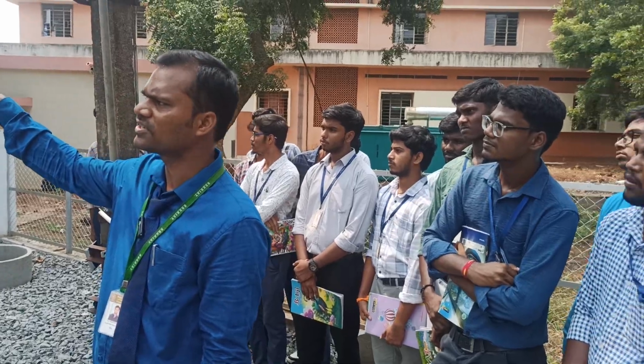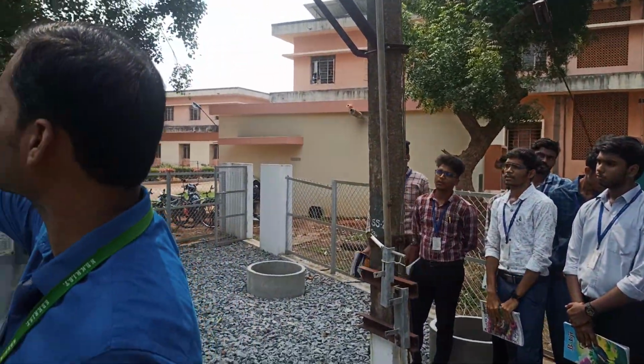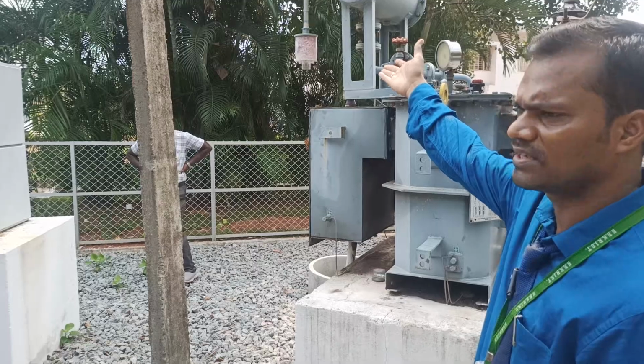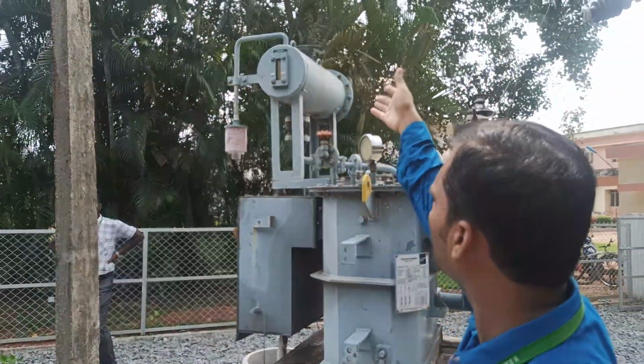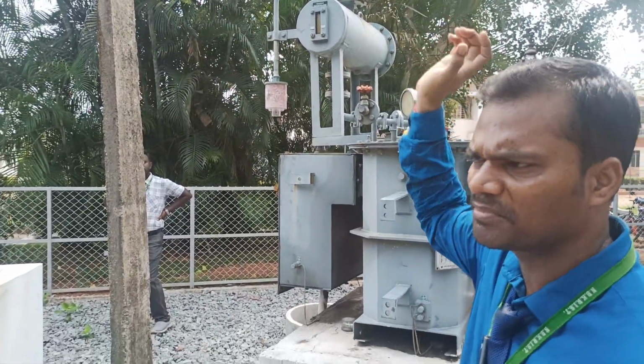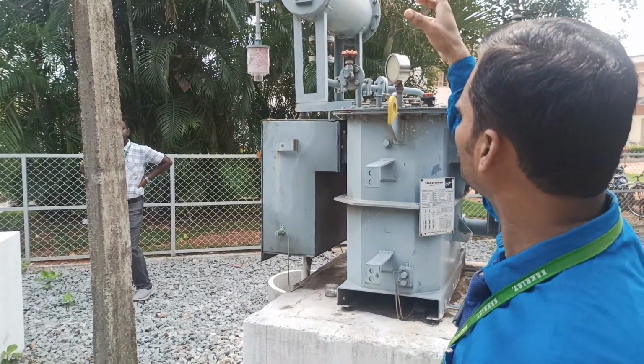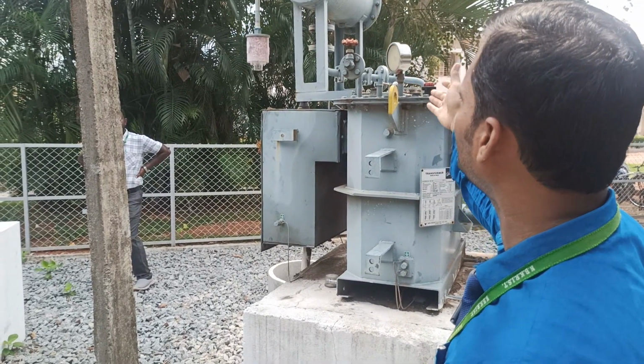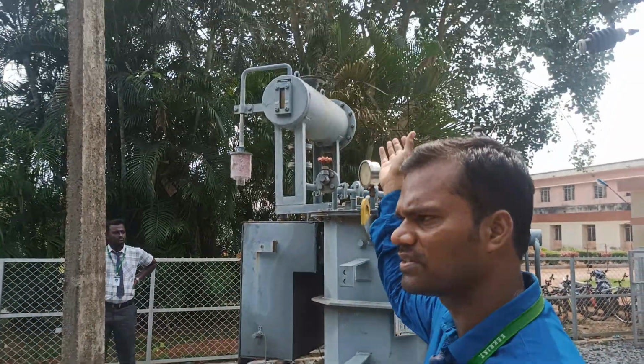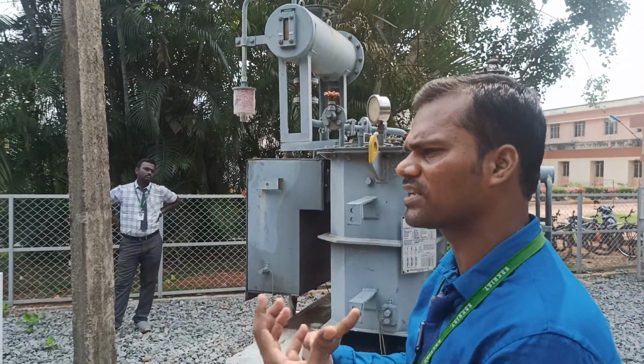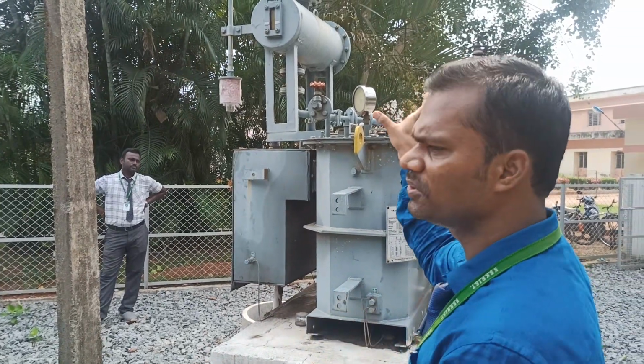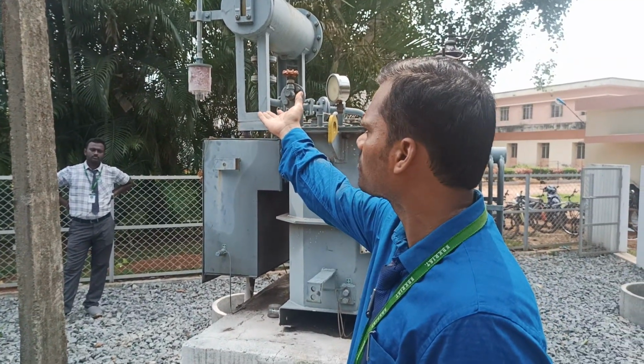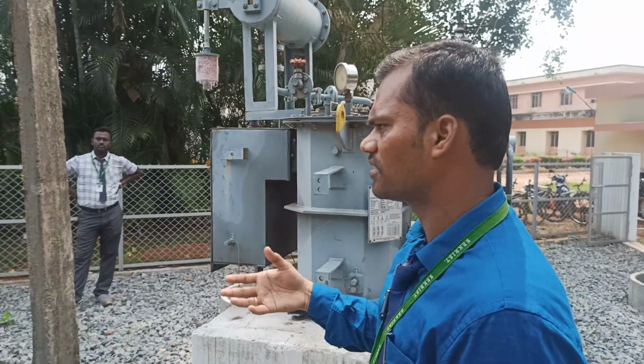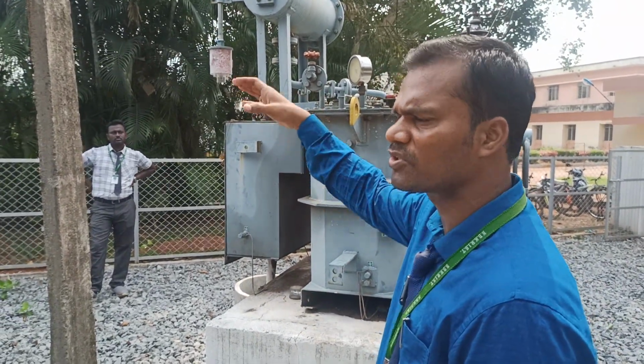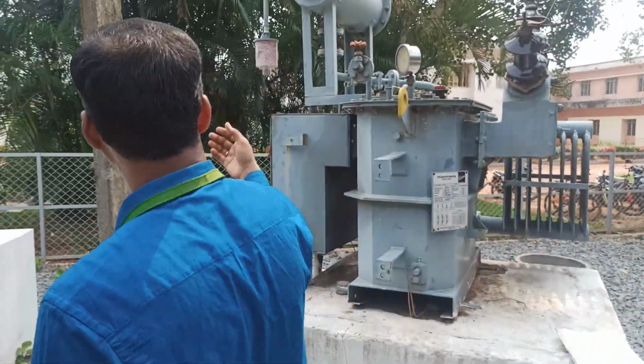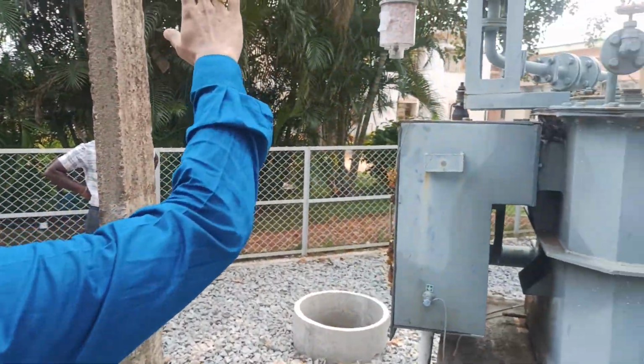So this porcelain will act like an insulator. You must have studied this in the transformer. This is like a breather, where we have silica crystals which absorb the moisture, and at the top what we are going to have is nothing but a conservator tank. Through the conservator tank we have a Buchholz relay. It will try to maintain the required pressure in the tank as well as in the oil. Conservator means balancing. Whatever oil is required, it will try to balance, and it will absorb moisture from the air. Sometimes in the winter season, moisture will be there outside, and that should not directly go into the transformer. The moisture is filtered out using silica gel crystals. So this is like an overall view.